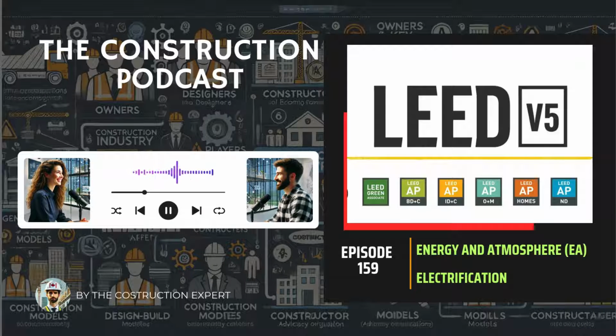Okay. Heat pumps, though, because they move heat instead of just making it, can get COPs of 2, 3, sometimes even 4 or 5. Wow. So requiring a COP of 1.8 means you can't just use inefficient electric resistance. You have to use efficient tech, mainly heat pumps. It's saying, go all electric, but do it smartly. Makes sense. Are there nuances to that COP rule?